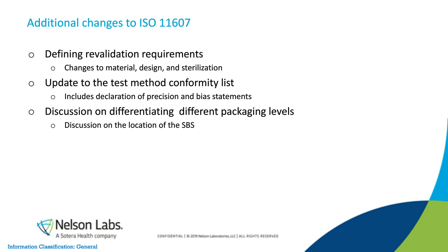It's also important that anything that compromises the original validation parameters or the integrity of the sterile barrier system, or SBS, is what drives whether your revalidation requirements are needed.